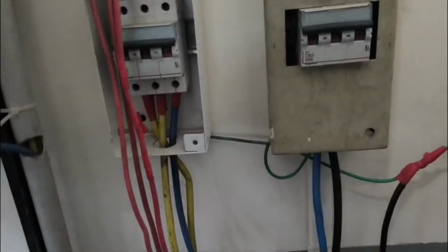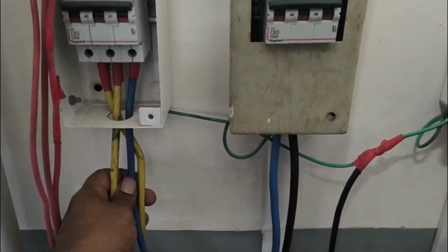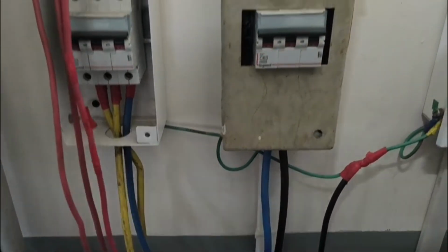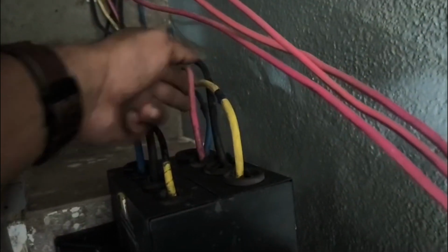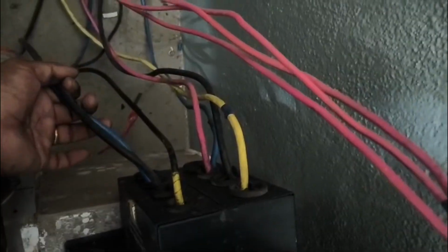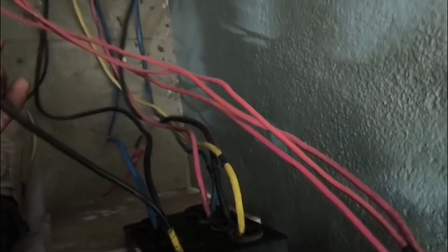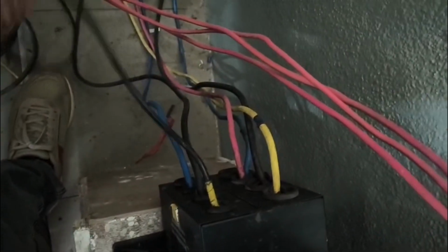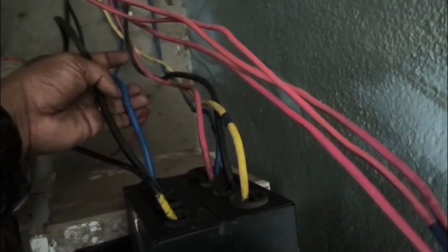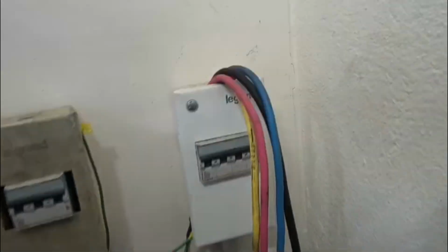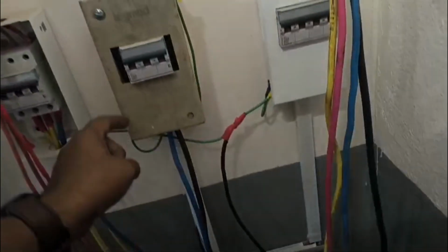So as I said, there are 3 terminals coming out. One is positive, the other two are negatives, and it is fed into the inverter. And then this is the AC input supply. This is R, Y, B and neutral, which is fed into the inverter as input, and these two are the AC output, and this is the ground for the inverter. So this is the positive phase and neutral to the load. It is connected over here and fed into the load. Okay, it is fed into the load through this MCB.